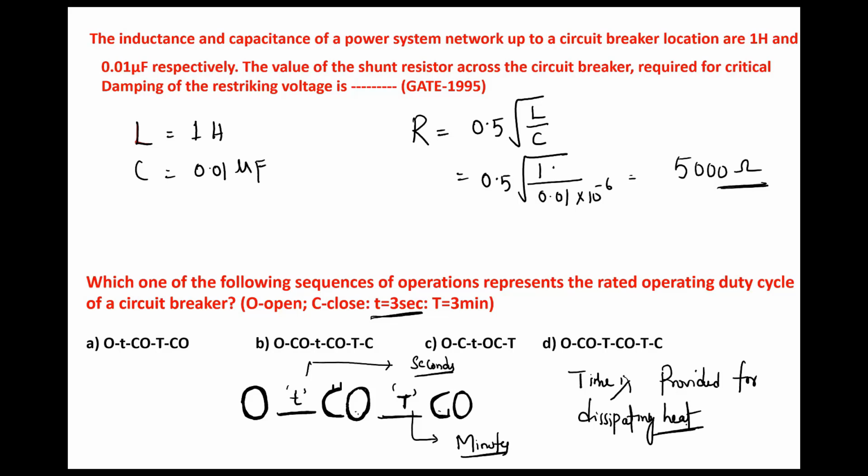So that is the operating cycle. Open, few seconds gap, close, open, few minutes of gap, close. Again if it opens, you should not touch that breaker. You should completely service that breaker. You can see if any permanent damage to the breaker happened, then only you have to put it into operation. So that is the operating cycle of the circuit breaker. I hope you have understood.